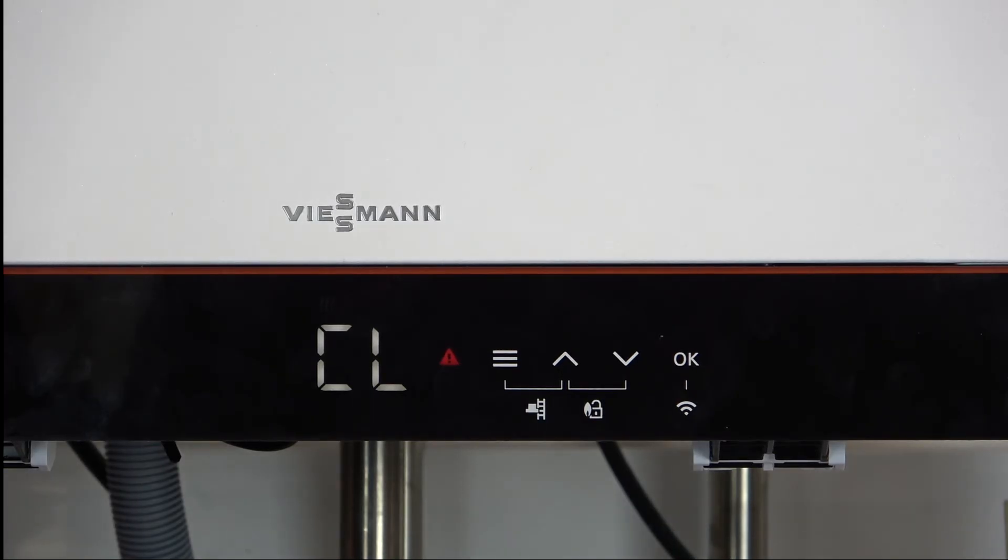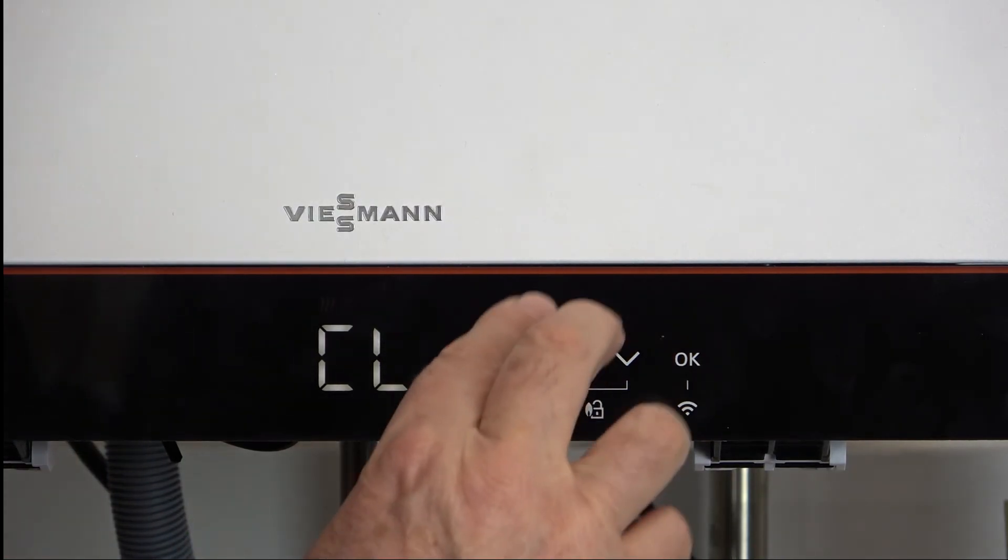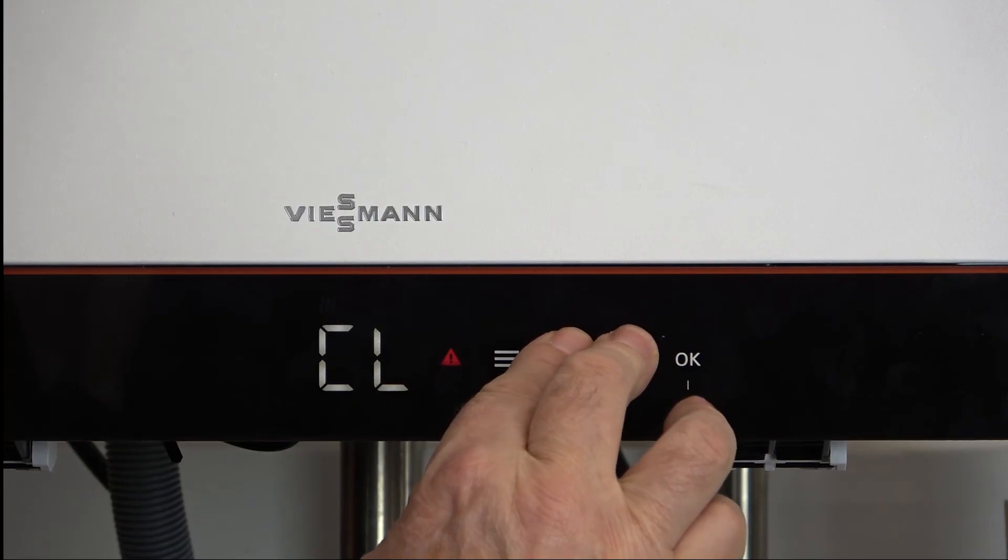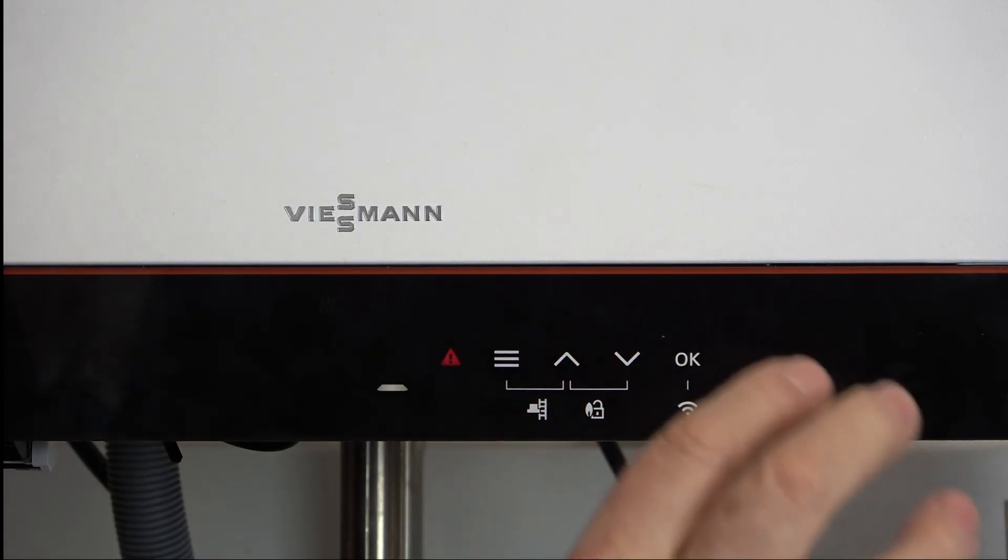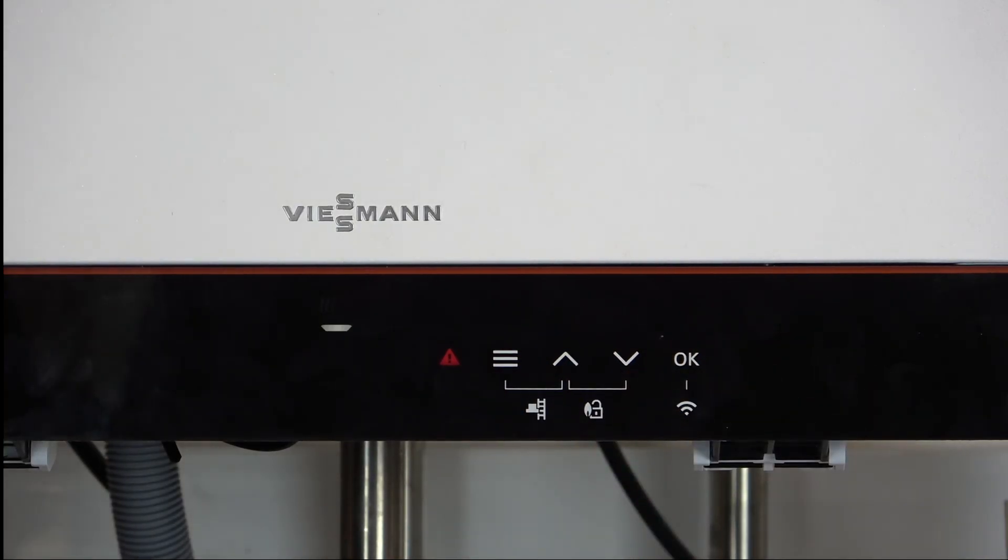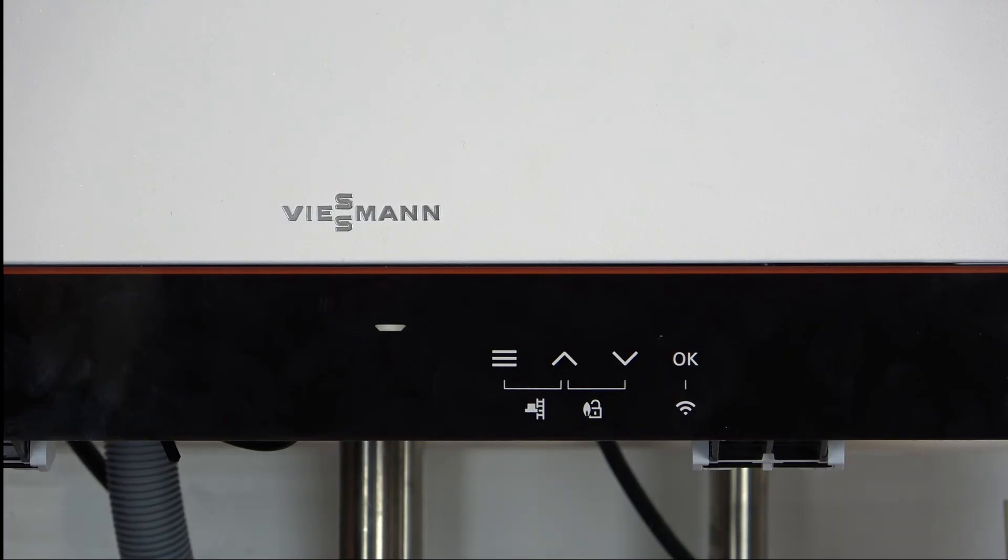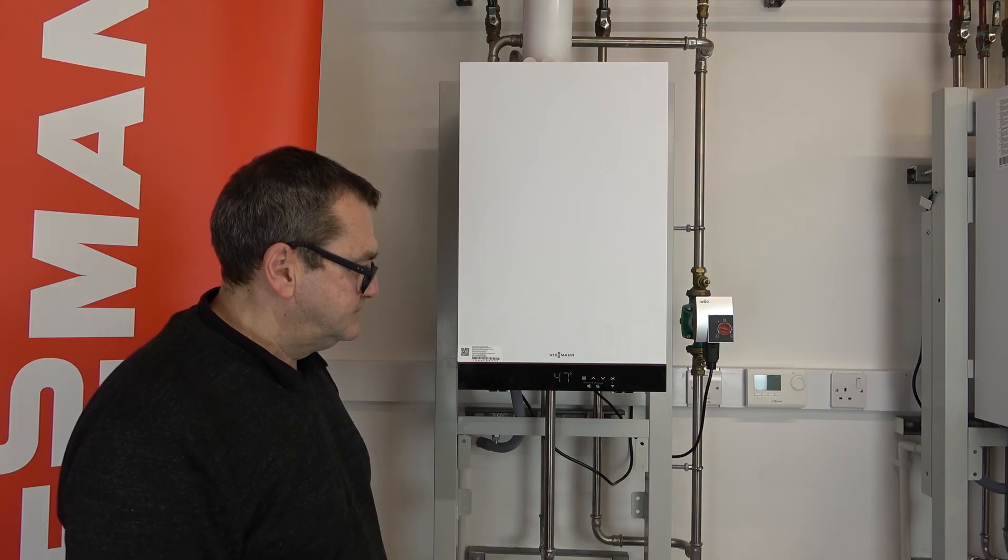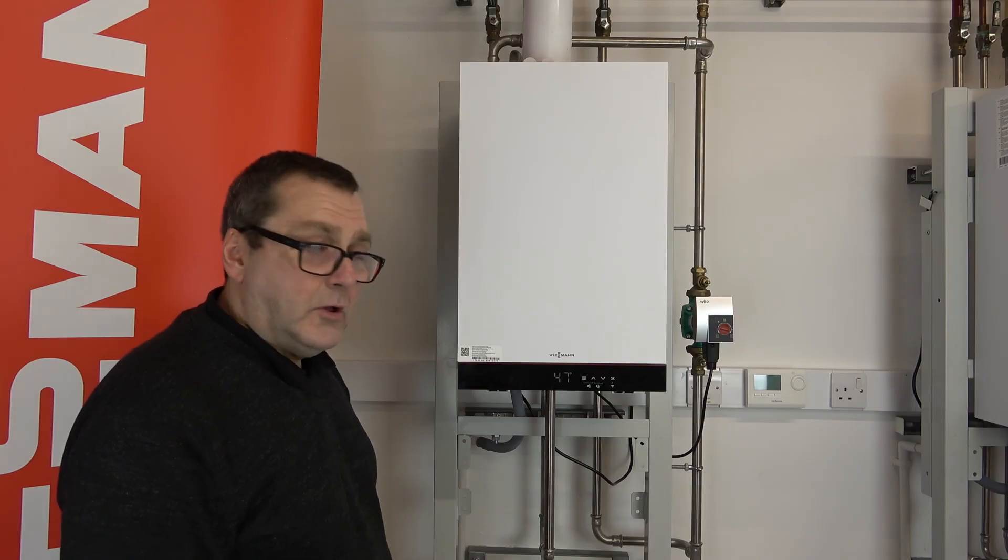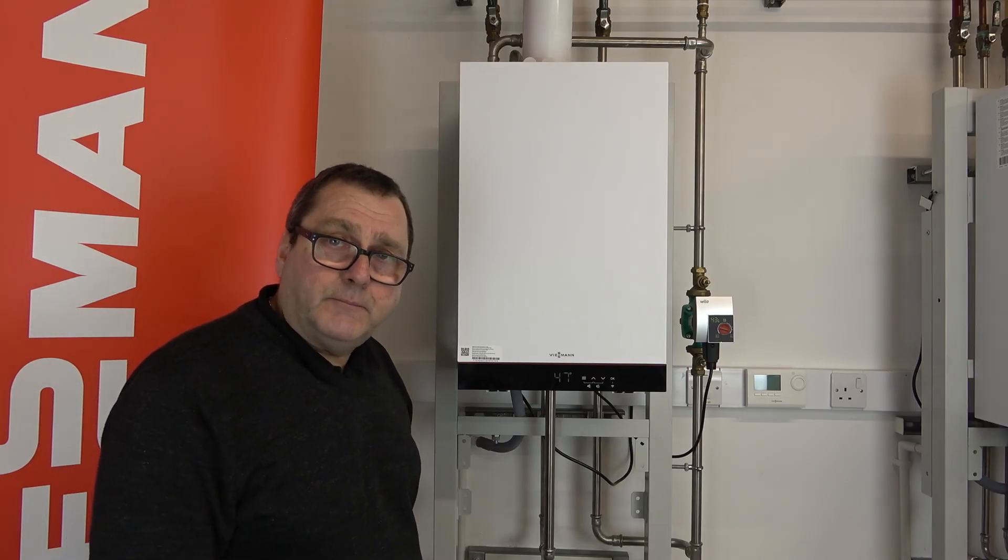So to reset the boiler it's a nice deft touch. As soon as we see the snake appear let go. So it's just a nice easy touch on the front, as soon as it appears let go and now we'll see that the boiler will reset itself. CL appears, OK, and then we're back at the main screen. The boiler is now ready to go again.